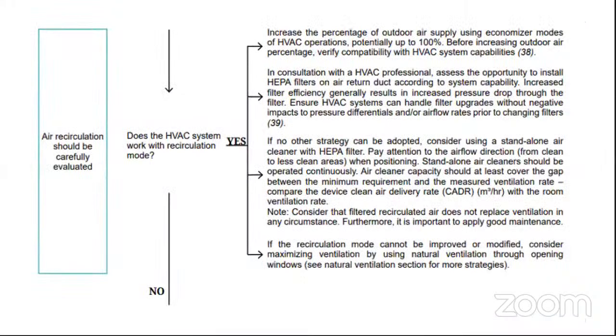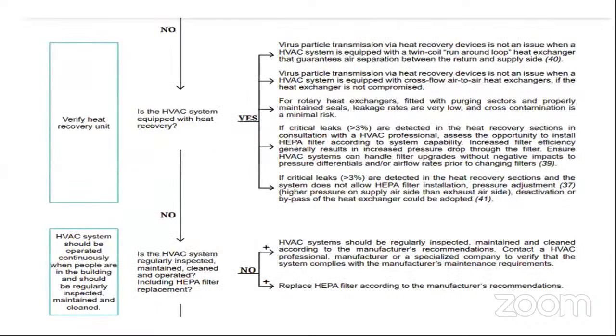Similarly, does the HVAC system work with recirculation mode? Now we need to make sure that the outdoor air percentage is higher when we are talking about the HVAC system. That needs to be done in consultation with an HVAC professional only. Increased filter efficiency generally results in increased pressure drop. We need a negative pressure inside the room where we have COVID-19 patients. Any kind of recirculation mode will not be used for the air supply to the COVID-19 patient. The same air cannot be circulated in the other areas of the hospital.